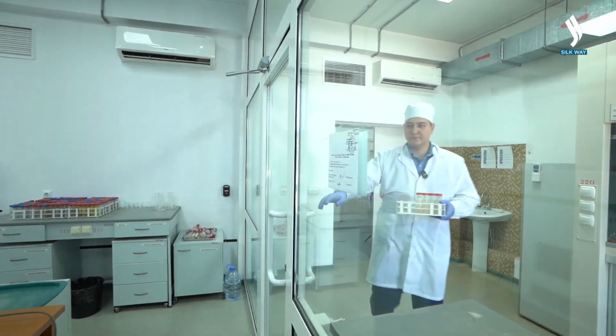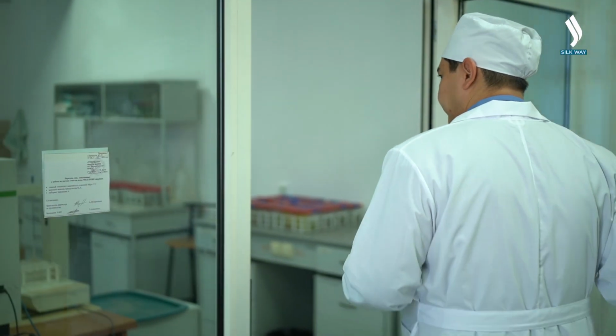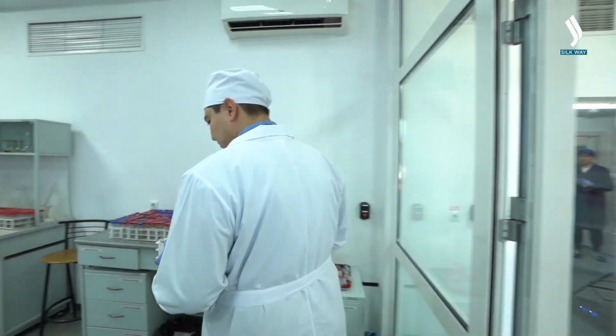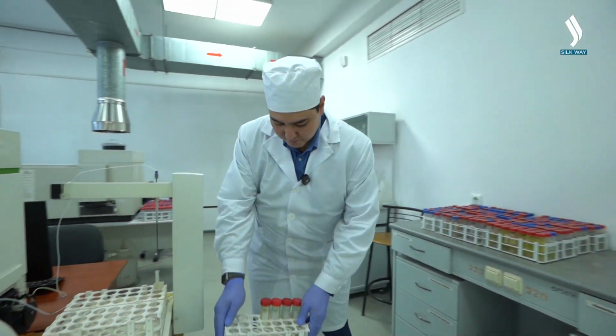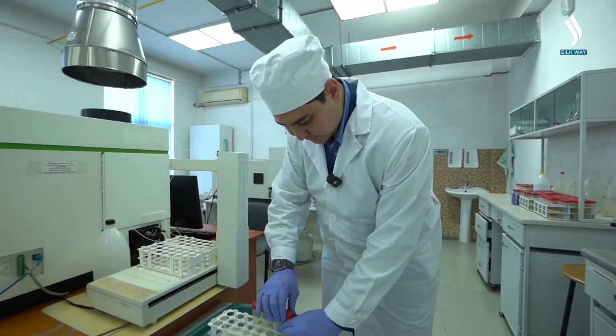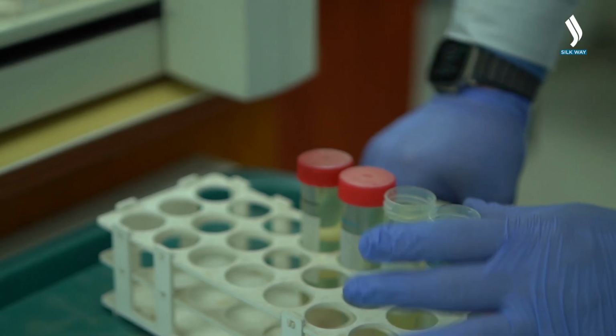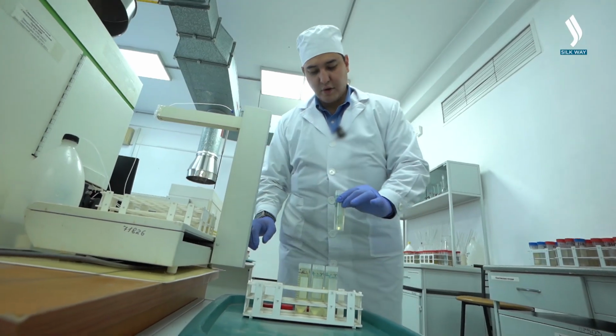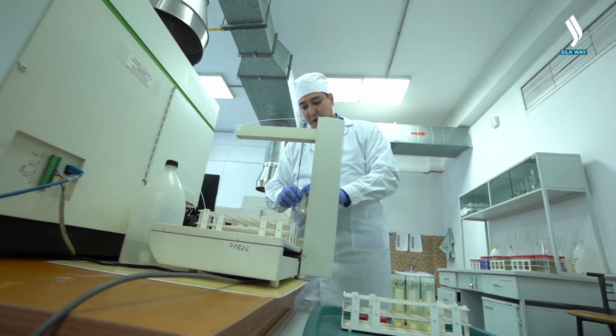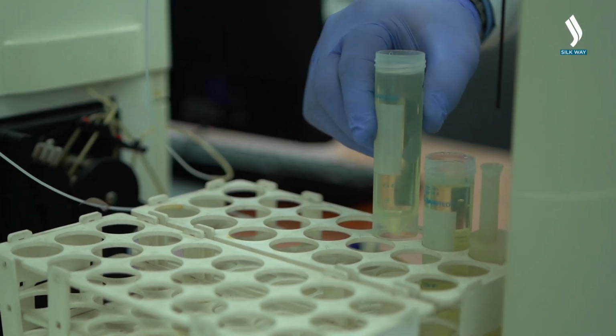The final stage is sample analysis using an optical emission spectrometer. This equipment determines the exact concentration of rhenium in the liquid samples. The prepared solutions are placed into the system, and each test takes about 5 minutes. The results are displayed on the computer screen.